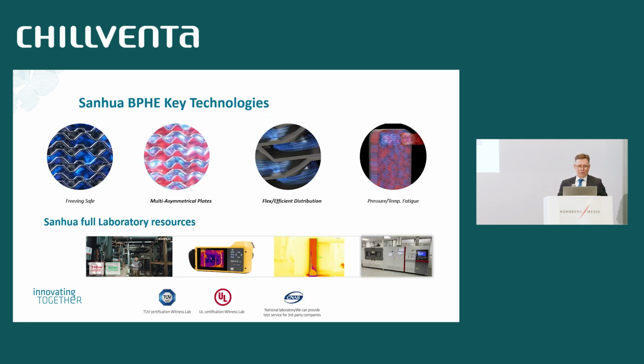At Sanhua, we work with different key technologies. One, as I mentioned before, is freezing protection, because you don't want freezing inside the heat exchanger. So you design the plate pattern to be optimized for avoiding freezing. We also have these multi-asymmetric plates, as I mentioned - two-dimensional asymmetry, between the water channel and the refrigerant channel, and also all over the plate.